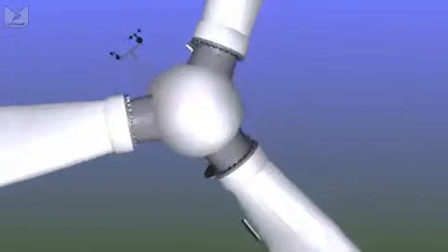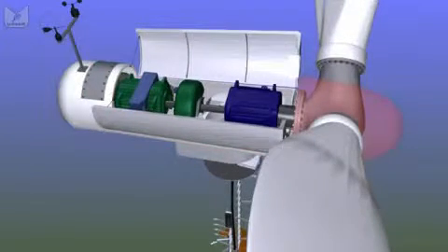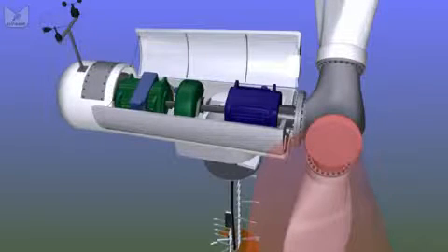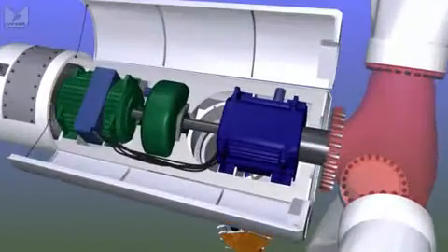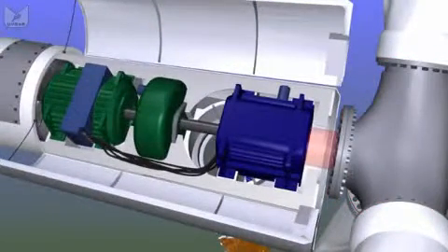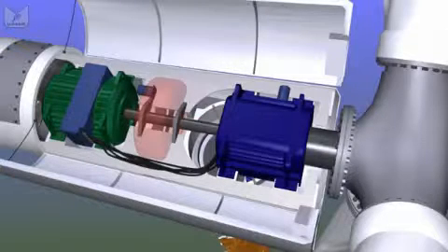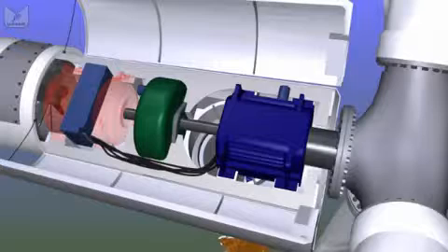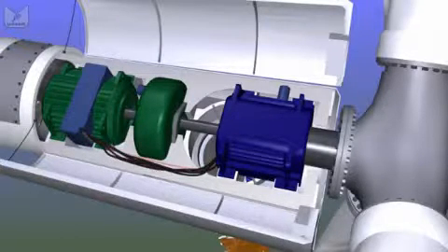At the front we have a similar fiberglass cowl protecting the hub, which is a steel casting on which we have bolted our 3 blades, and the blades can turn or pitch so that the angle they form with the wind can be varied. Out at the back of the hub we have a shaft which leads into the gearbox, then a high-speed shaft through a brake into a generator, and that generator then supplies the electrical power, as I say, at about 690 volts all the way back down the tower to the base.